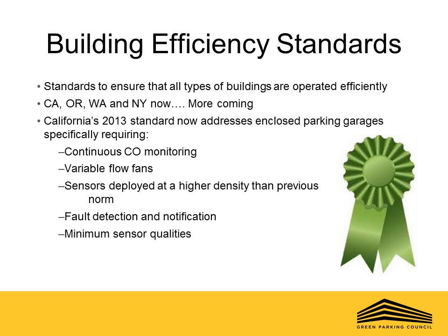An analogy that I commonly use in this respect is tires on an automobile. If you want them to continue to perform safely and efficiently and with a maximum life, you've got to watch your air pressure, rotate, balance, etc. So there is periodic maintenance on those tires to make sure that you're again maintaining safety and efficiency. Similar with the carbon monoxide sensors, the way they interact with the gas in the air, they do require periodic maintenance, not only in terms of the hardware itself, but again, humans can sometimes intervene, an operator leaving a fan in a hand-on mode or a hand-off mode.